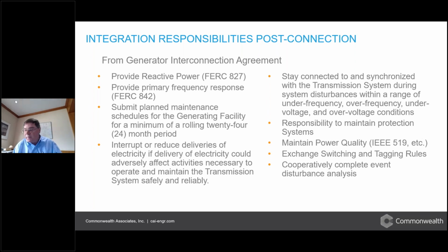You have to continue to provide reactive power. You can't just test the thing and say, I'm done. So 827, you've got to continue to do that. There's actually a MOD 25, which is capability testing that is required on a regular basis throughout the life of a project. You need to continue to provide primary frequency response. You need to submit maintenance schedules. You may get interrupted and curtailed if there's a grid problem.